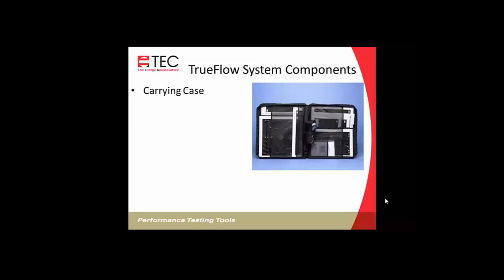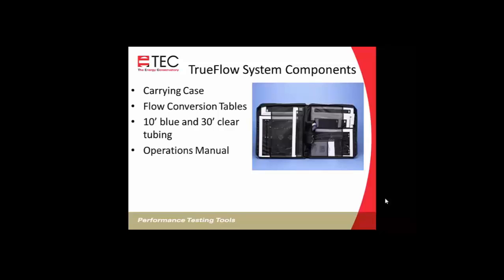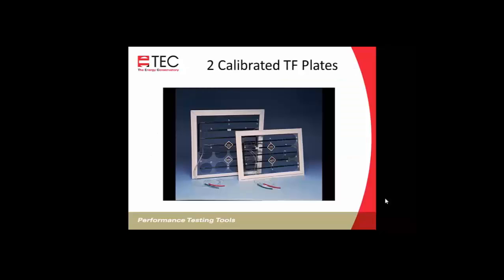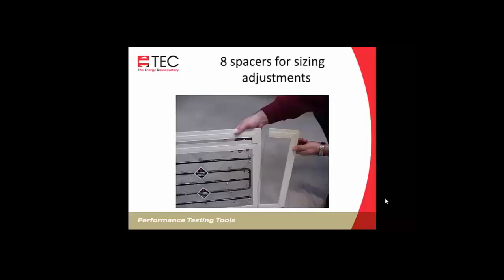So the components include the carrying case pictured at the right. Everything neatly fits into that carrying case, and it folds in half and zips up and has that carrying handle to move it around. It includes some laminated flow conversion tables if you're not using the pressure and flow gauge. It has a 10-foot blue and a 30-foot clear tubing, and an operations manual, along with the 2 calibrated plates, the 14 by 20, the number 14, and the 20 by 20, number 20 TrueFlow plates. Comes with both of those, along with 8 spacers for sizing adjustments, and so it'll fit the most common filter sizes.